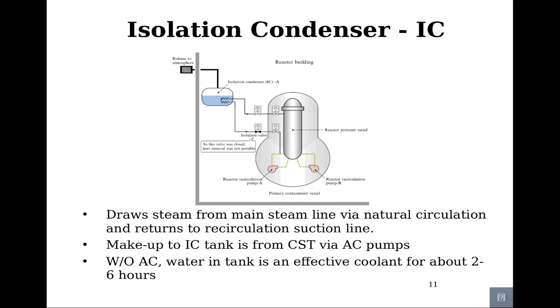Unit 1's emergency core cooling system was made up of isolation condensers. They draw steam from the reactor, pass it through a heat exchanger, and return the condensate back to the reactor. However, alternating current is required to fill up the heat exchanger. Without water addition to the coolant side, it only has 2 to 6 hours of cooling capacity.